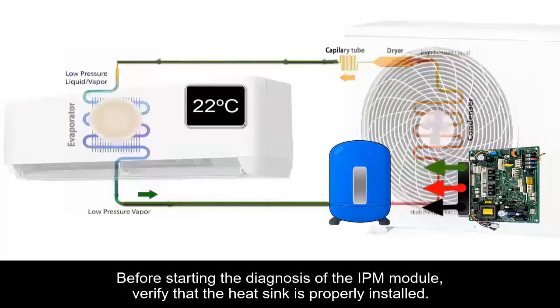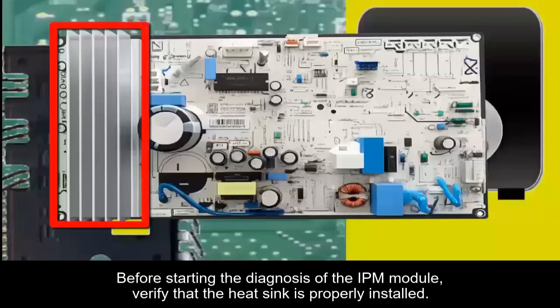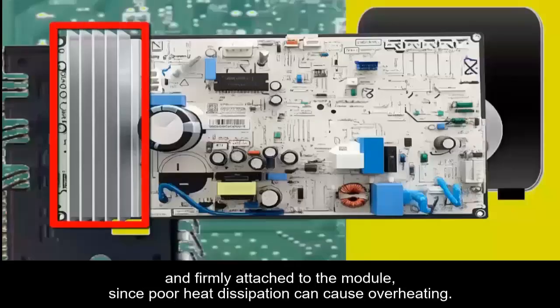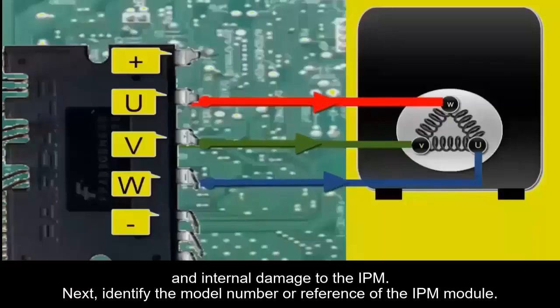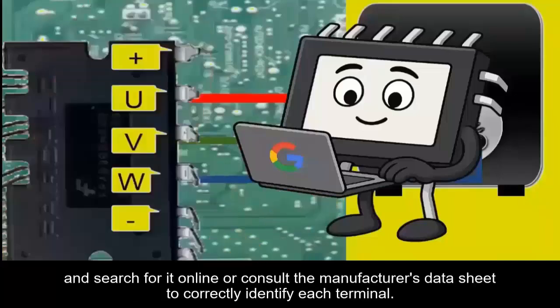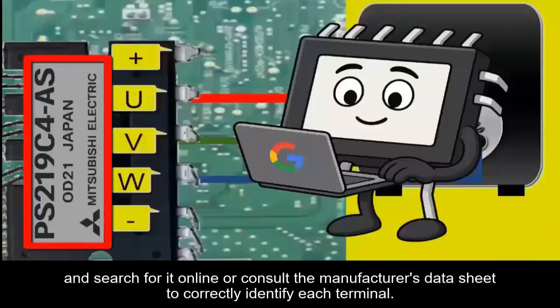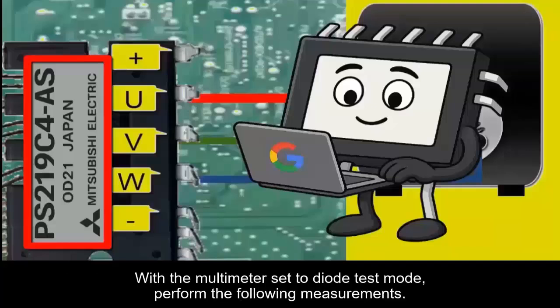Before starting the diagnosis of the IPM module, verify that the heatsink is properly installed and firmly attached to the module, since poor heat dissipation can cause overheating and internal damage to the IPM. Next, identify the model number or reference of the IPM module and search for it online or consult the manufacturer's datasheet to correctly identify the function of each terminal or pin.